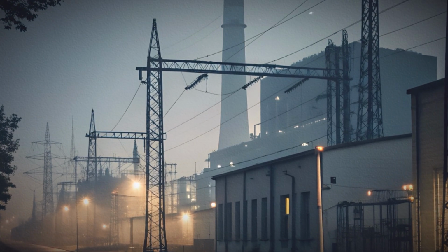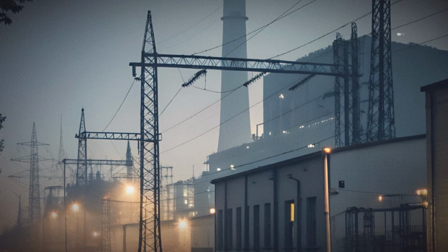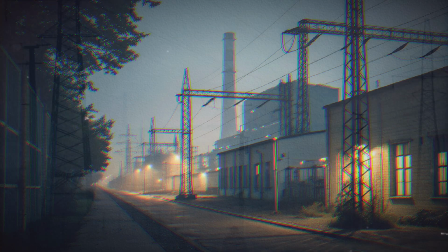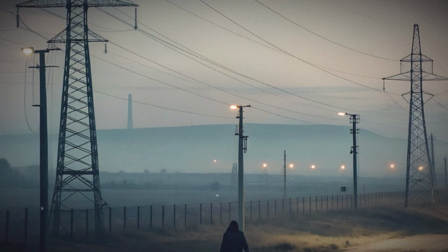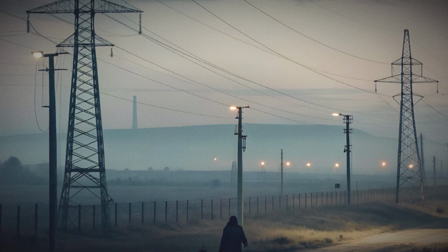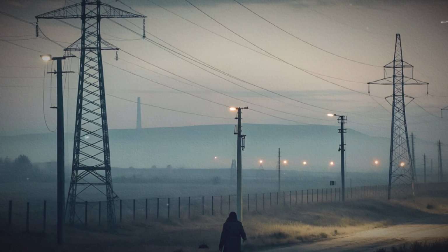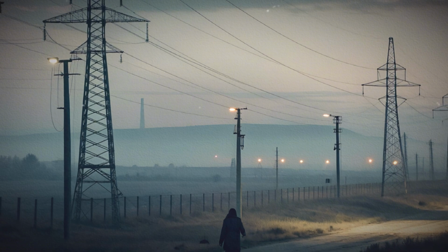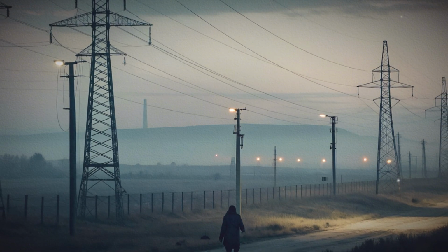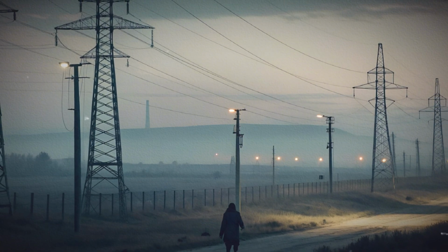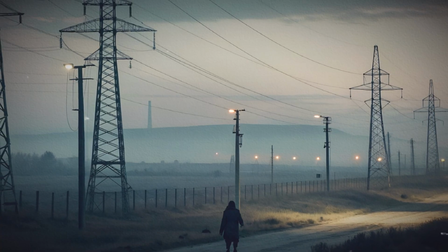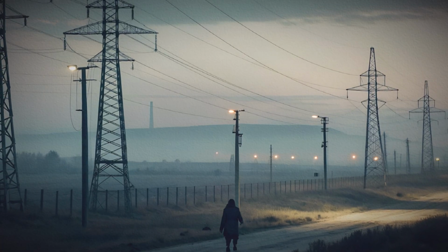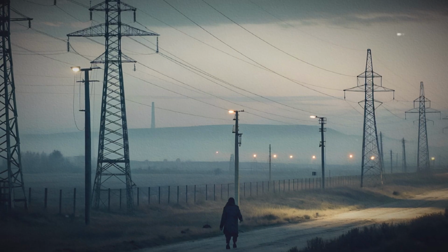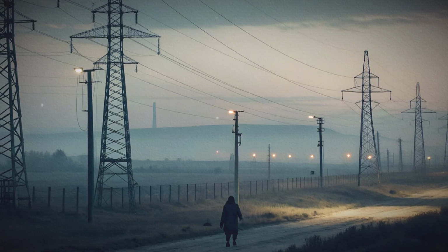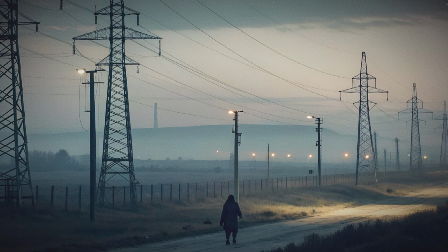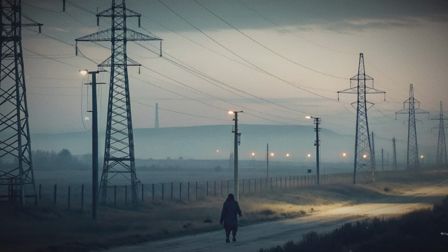Transmission lines typically operate at tens to hundreds of kilovolts. Those voltages are not arbitrary. They are chosen to balance technical performance, cost, and safety. Higher voltage allows power to flow with smaller current. Smaller current means less energy lost as heat in the conductor. At the same time, higher voltages require larger insulators, taller towers, and greater clearances. Engineers select voltage levels that match the distance and capacity required for a particular corridor.